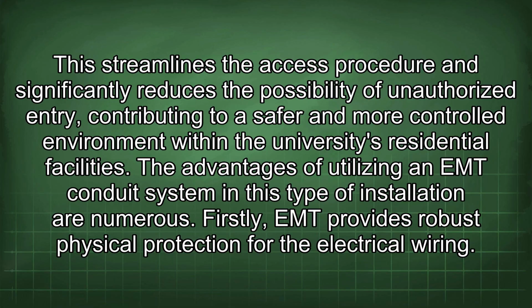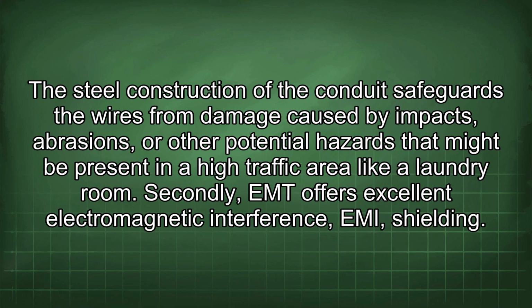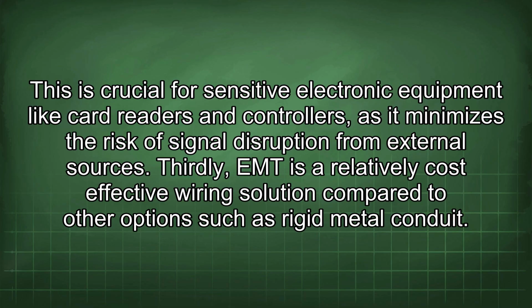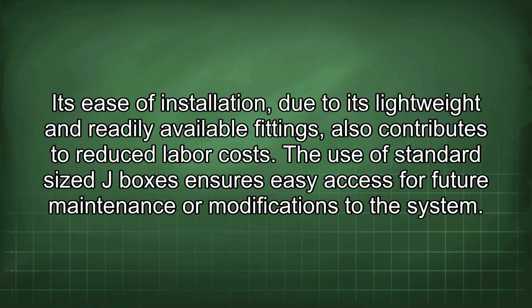The advantages of utilizing an EMT conduit system in this type of installation are numerous. Firstly, EMT provides robust physical protection for the electrical wiring. The steel construction of the conduit safeguards the wires from damage caused by impacts, abrasions, or other potential hazards that might be present in a high-traffic area like a laundry room. Secondly, EMT offers excellent electromagnetic interference (EMI) shielding. This is crucial for sensitive electronic equipment like card readers and controllers, as it minimizes the risk of signal disruption from external sources. Thirdly, EMT is a relatively cost-effective wiring solution compared to other options such as rigid metal conduit. Its ease of installation, due to its lightweight and readily available fittings, also contributes to reduced labor costs.